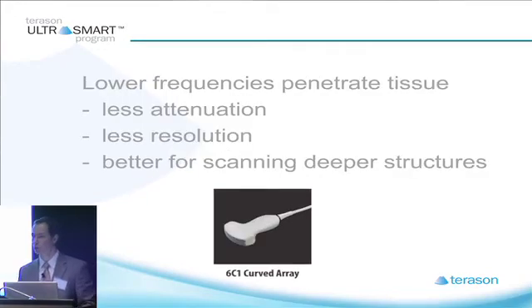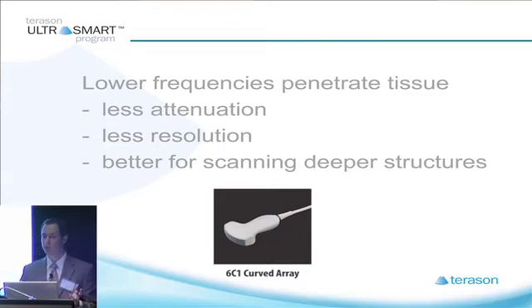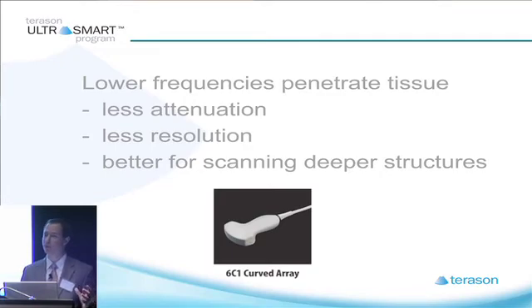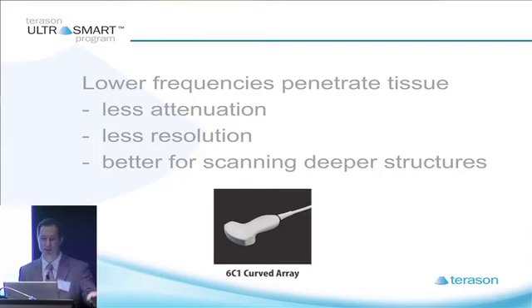That's when you want to use a curved array, also called curvilinear arrays. They're lower frequencies — 6 megahertz down to 1 megahertz — still above the 20k that defines ultrasound. You get less attenuation, but you have to compromise something: in this case you'll compromise some resolution, but you will get to penetrate deeper tissues and get better imaging of deep structures than you would otherwise.